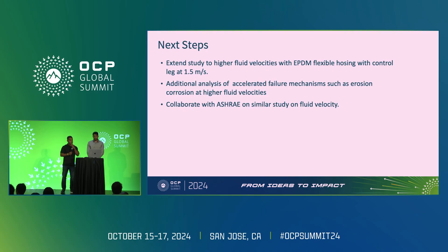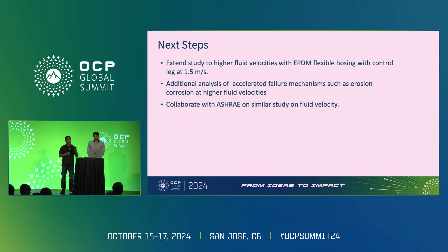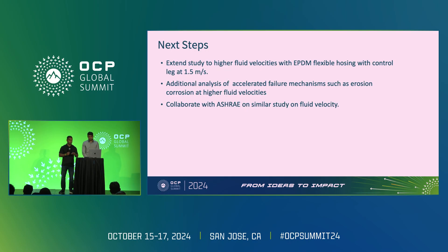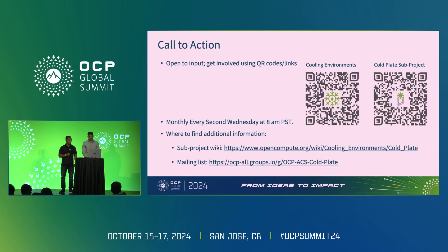In terms of next steps, we want to focus on the control leg at 1.5 meters per second and do additional analysis of the copper surfaces at higher fluid velocities. We're also working with ASHRAE on the RTAR with Mark Stenke and others to try to address this and see if we can get the limits updated if needed, given the feedback we're getting from various folks on the justification behind the 1.5 meters per second fluid velocity limit. As a call to action, please do join the cold plate subproject and cooling environment calls. Thank you all for sticking around — let us know if there are any questions.